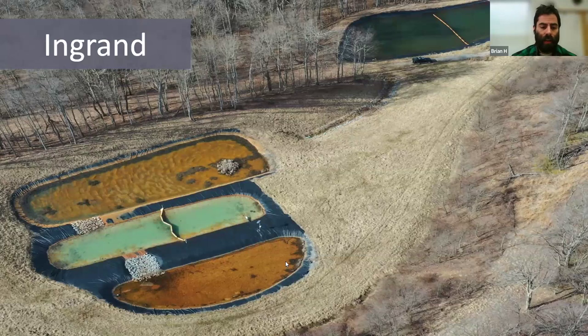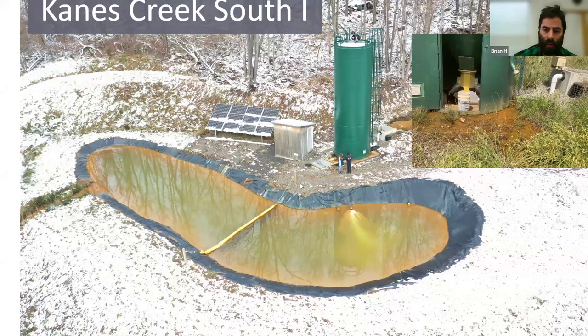Here is one of Friends of Deckers Creek's passive sites. The acid mine drainage collected along this old high wall goes into the first pond, second pond, third pond, fourth pond, fifth pond, and at the end you're getting good water quality. Notice there's no doser or silo. Then we have our active site — here the water is coming in from right behind this picture, going through the treatment system and into our settling pond. Inside the silo is a tipping bucket that delivers a dose of lime to the treatment system.